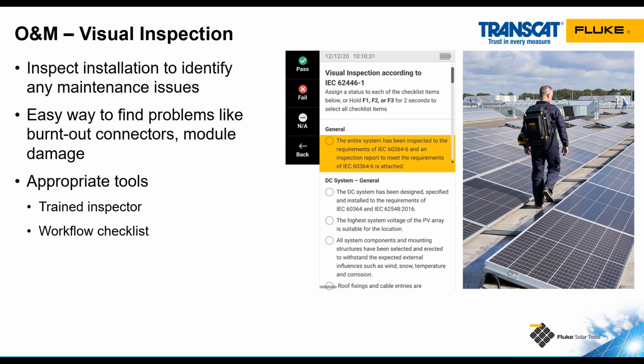This is a picture from the SMFT 1000. It has a built-in checklist based on that IEC standard. That standard has a whole list of items that need to be visually inspected before you do any physical tests. With the SMFT 1000, you can very easily hit pass, fail, or not applicable to each of those items in that standard. You can save that information, and then you can report it out later if you needed to show that you actually did the visual inspection.